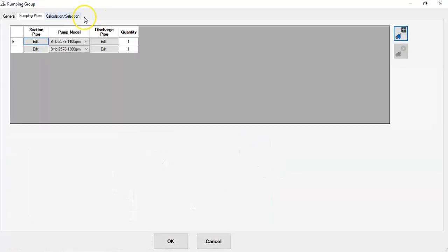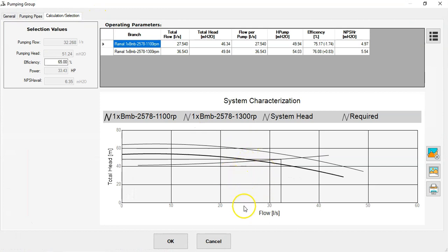When we return to the results, we see a new row in the table of operating parameters with the new pumping pipe and pump added. We have then that, for this condition, it is possible to overcome the required flow rate by about 4 liters per second. And, still better, we see that the pump model is operating practically at the point of best efficiency, a much more desirable condition than for the first option. In this way you could continue studying the operation not only for other rotational speeds but, of course, for other pump models. In a very simple way with PLUMBER.